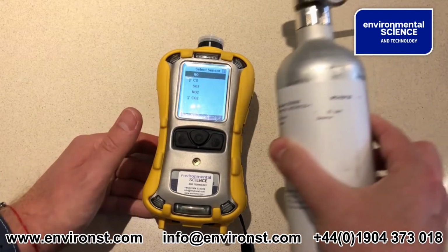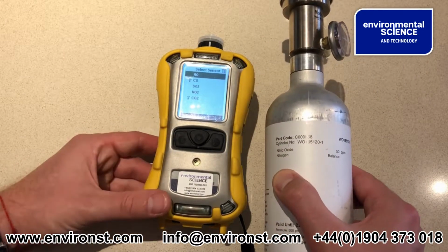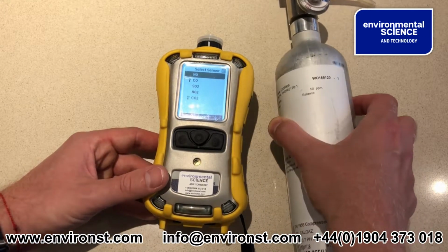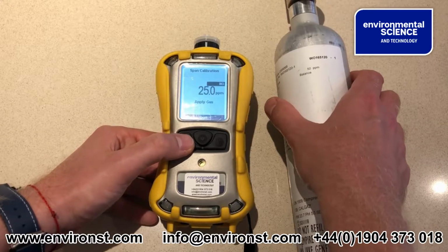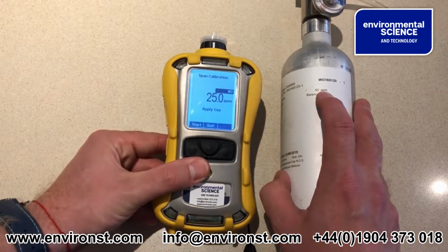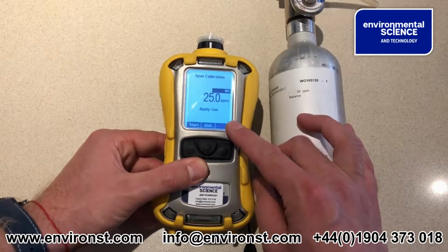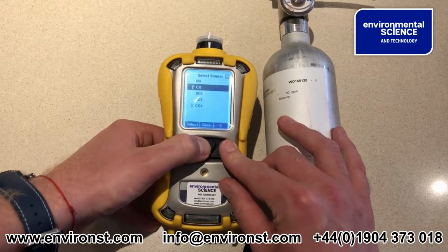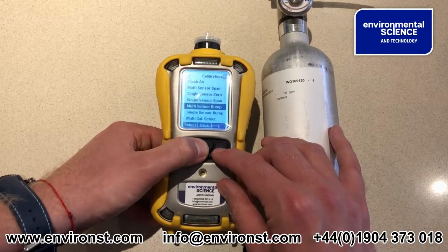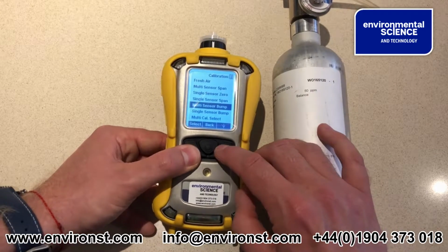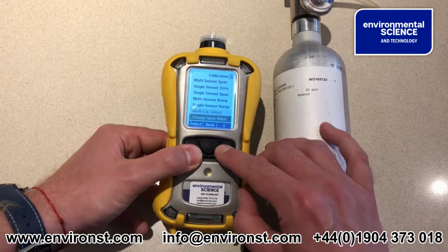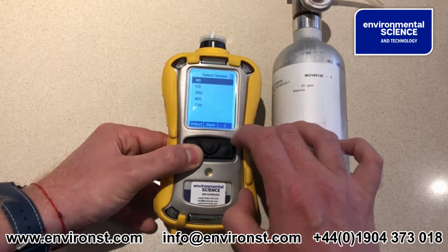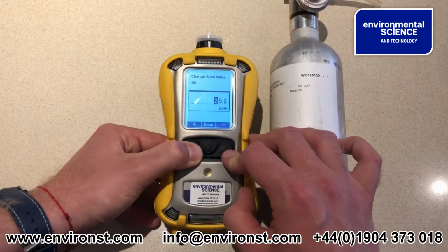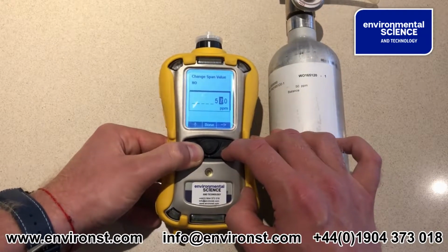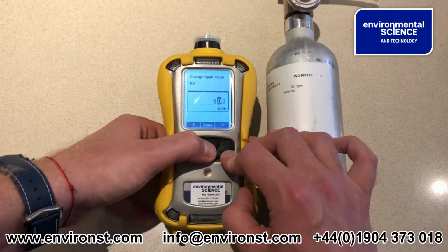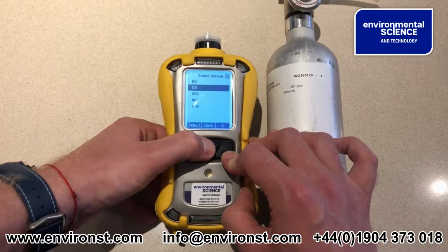Now, today I've got nitrogen monoxide, so nitric oxide, and I'm going to select from here nitric oxide and do the calibration. Now what you can see here is this is 50 ppm and it's saying that it wants to calibrate at 25. So what we need to do is come back out of here, come back again, and this is where we go and change the concentrations of the calibration gases. So if I go change span value, nitrogen monoxide, and I need to change this to 50. And say done, save, let's go back again.